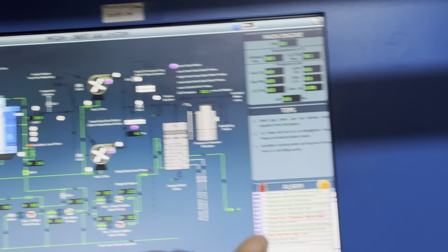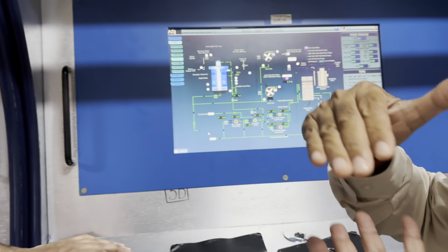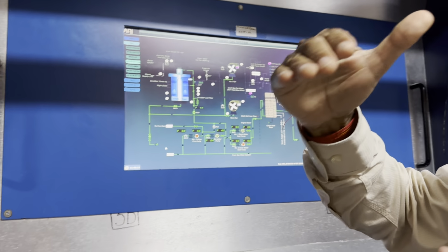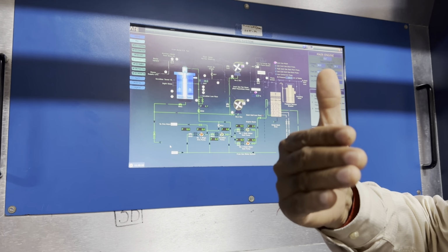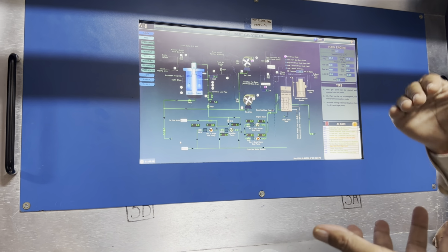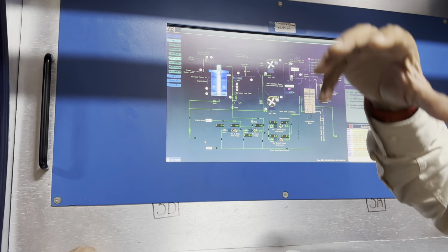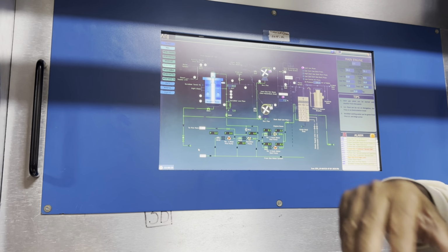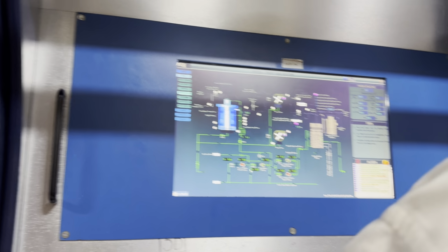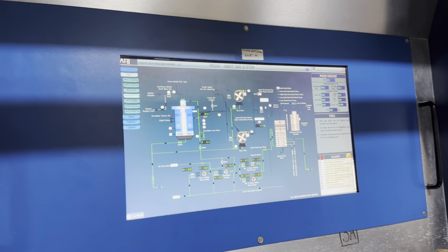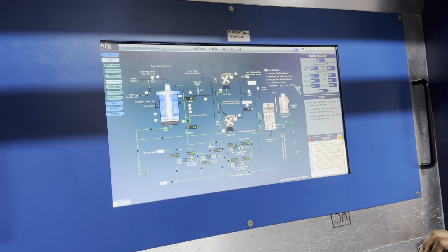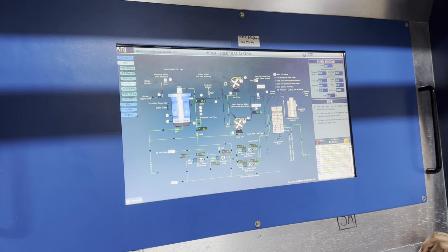Now I have time to explain to you, please. The tank you cannot load full because you have to leave space for accommodating the expansion and contraction, correct? Yes, sir. So in the contraction, if it goes in cold season, it will come under vacuum. Then the PV breaker and PV valve, the pressure vacuum breaker, PV valve in each tank.